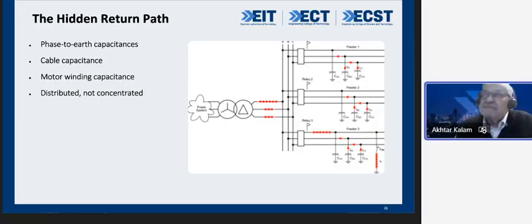I've drawn all that circuit. I've shown you how the phase to earth capacitance is there, how the cable capacitances are there, how the motor winding capacitances are there, how it is distributed, not concentrated. The fault current did return, but it did not go through the soil. That is the hidden truth. There was a return path, but it did not come through the soil.